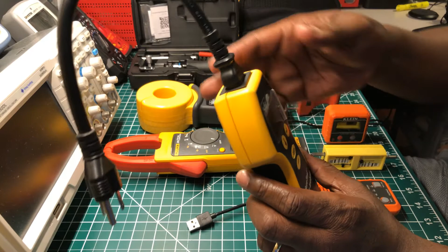I also use this when checking those receptacles with the built-in USB port. I use it to check if there's 5 volts, 0.5 amp or 1 amp coming out of there. Sometimes the 120 volt part works fine, but one of the USB ports could be damaged. So you want to check that. This is another circuit analyzer, put out by Fluke.